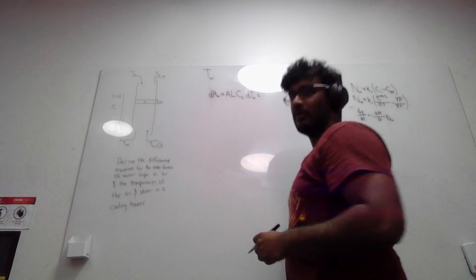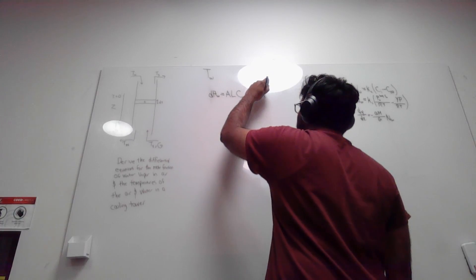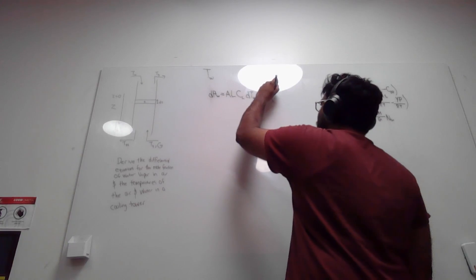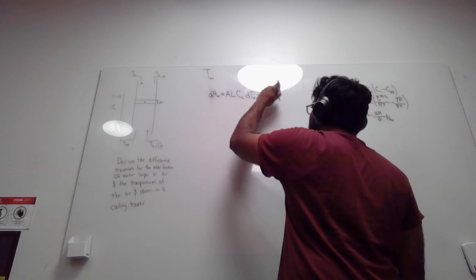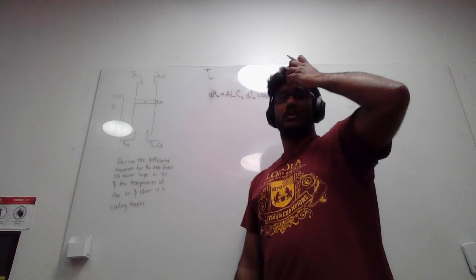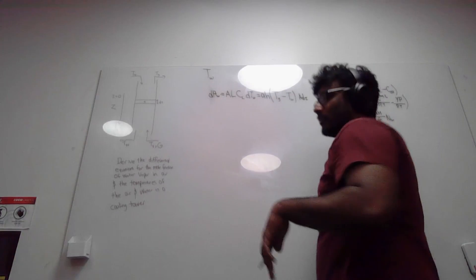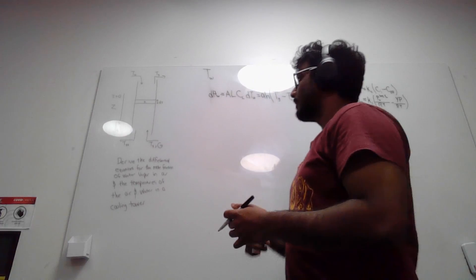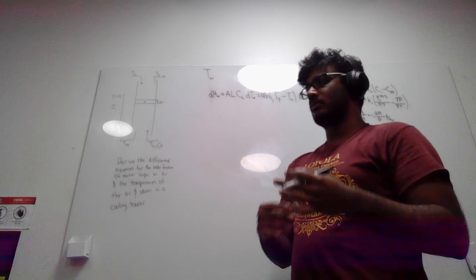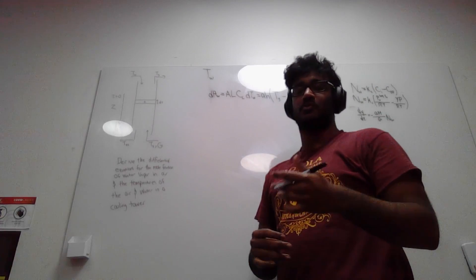Looking at the heat transfer specifically, we multiply the specific area times the heat transfer coefficient times the difference in temperature between the gas phase and the water, all times the differential volume a·dz. An important consideration is that with heat transfer there is also evaporation, and with evaporation water is leaving — meaning the temperature of the water goes down. So the evaporation term is subtracted from the heat transfer.